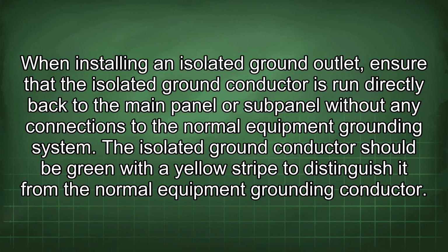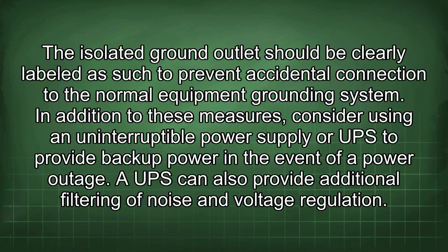When installing an isolated ground outlet, ensure that the isolated ground conductor is run directly back to the main panel or subpanel without any connections to the normal equipment grounding system. The isolated ground conductor should be green with a yellow stripe to distinguish it from the normal equipment grounding conductor. The isolated ground outlet should be clearly labeled as such to prevent accidental connection to the normal equipment grounding system.